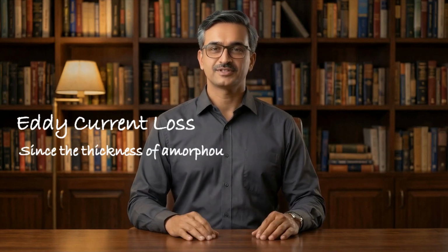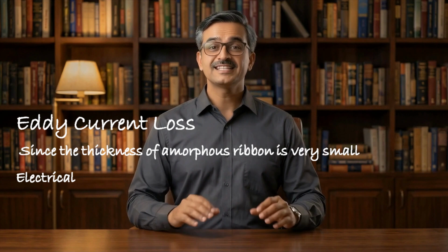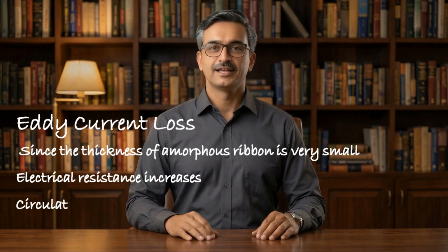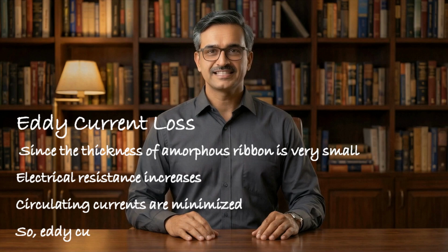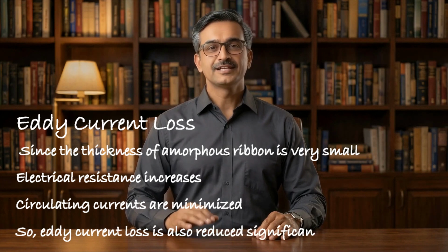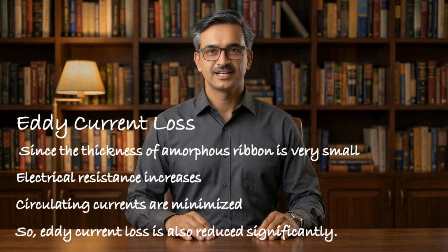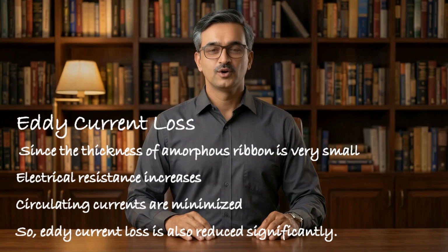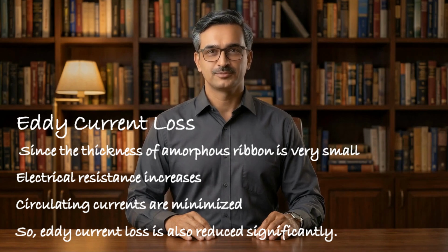Now coming to eddy current loss. Since the thickness of amorphous ribbon is very small, electrical resistance increases. Hence, circulation currents are minimized. Thus, eddy current loss is also reduced significantly. So overall, we can conclude that the amorphous core reduces both hysteresis loss and eddy current loss, making it highly efficient for distribution transformers, especially under no load or light load conditions. However, due to its lower flux density capability, the core size becomes slightly larger compared to a CRGO core.